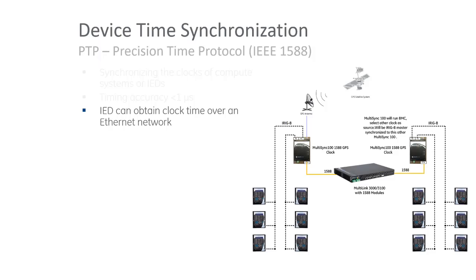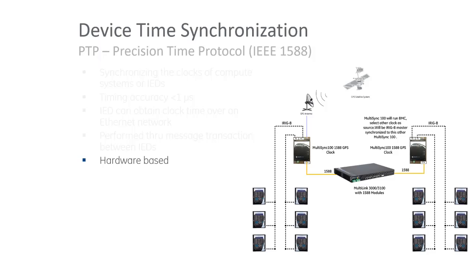All IEDs on the network are synchronized. If a network is built, relays, meters, and other devices already have access to it — all you need is a 1588 clock to broadcast the signal so all devices can synchronize. It is a hardware-based time synchronization method, meaning switches and end devices must support it, because achieving microsecond accuracy cannot be done in software — it takes too much processing time.